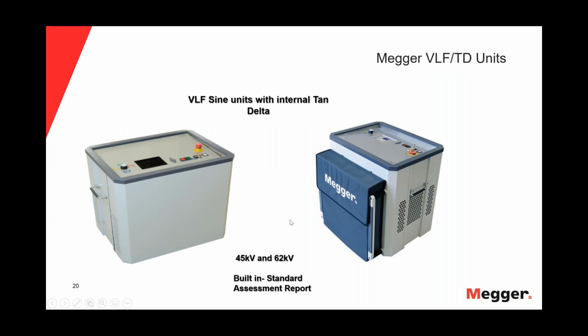What we have here is our product list for VLF sine units with internal tan delta. So here we have a 45 kV unit and a 62 kV unit. All of these units have a standard assessment reporting already built in. So these units not only have the VLF technology with the sine wave, they also have the built-in tan delta, so no need for an external connection or extra connections to be able to have your tan delta values. And all of the reporting that we just went over is also built into the assessment report.